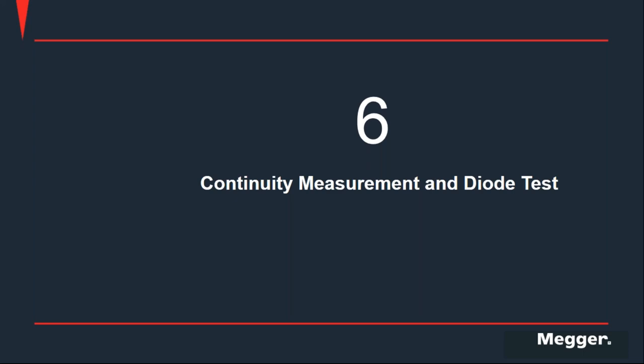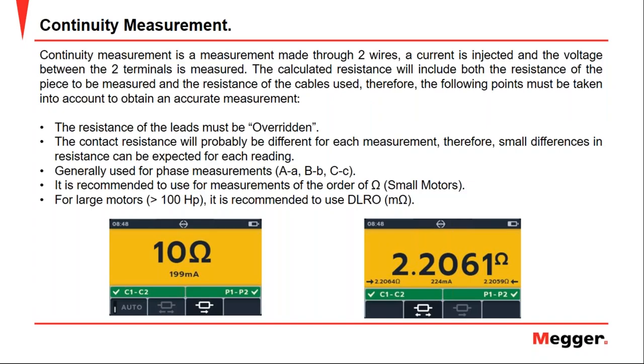Continuity measurement and diode test. The continuity measurement allows us to measure the resistance value between two points. However, through this method, both the resistance between the two points and the resistance of the cable used are being measured and affecting the readings. Therefore, certain aspects must be taken into account to try to make the measurement as accurate as possible.